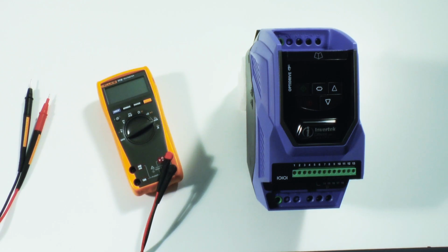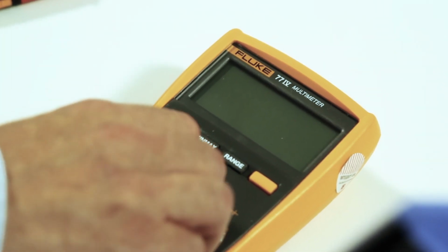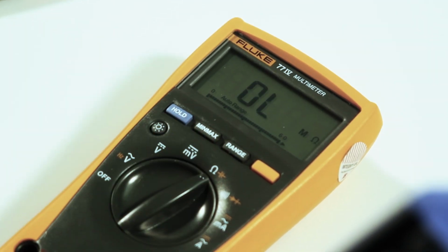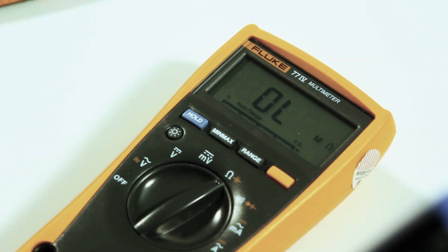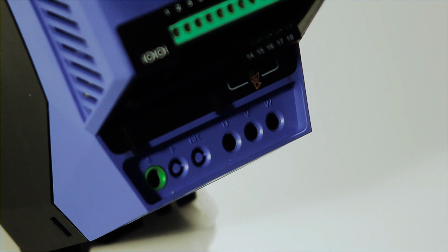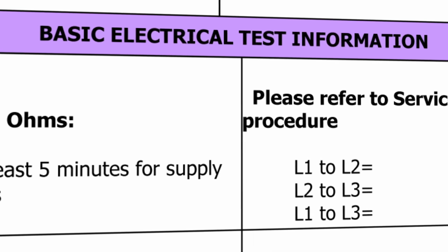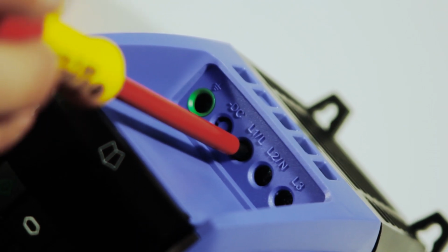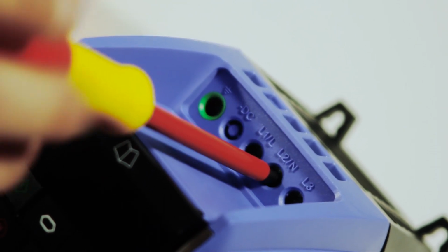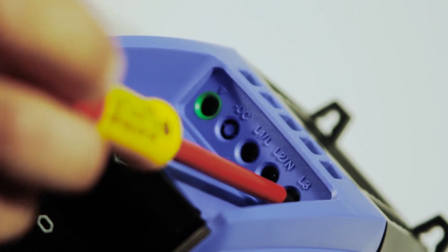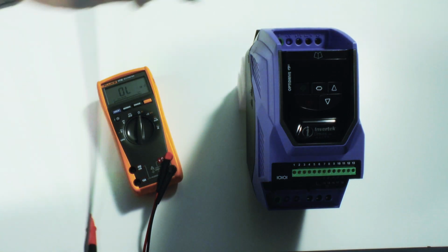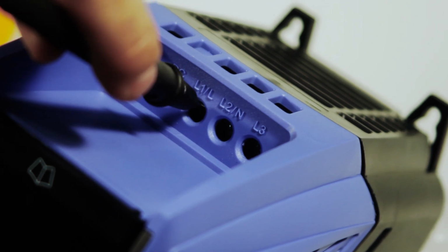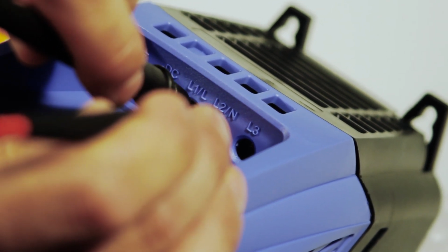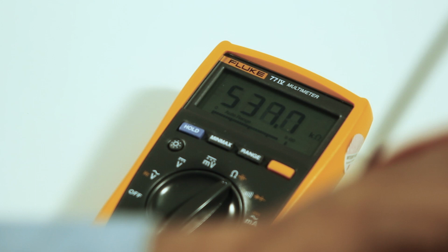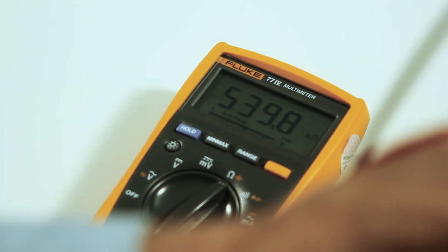The following tests can be completed without taking the drive apart. To begin, set your multimeter to read ohms and disconnect the drive for at least 5 minutes from the supply before completing these tests. Drive input check. Ensure terminal blocks are screwed down using the terminal screwdriver. Place the black multimeter lead on L1 and red multimeter lead to L2. Please refer to the service manual for comparison readings.